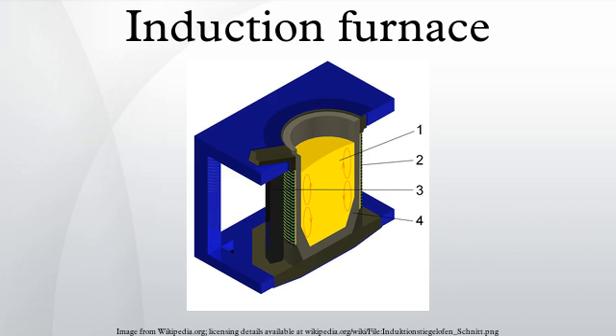Operating frequencies range from utility frequency to 400 kHz or higher, usually depending on the material being melted, the capacity of the furnace and the melting speed required. Generally, the smaller the volume of the melt, the higher the frequency of the furnace used.